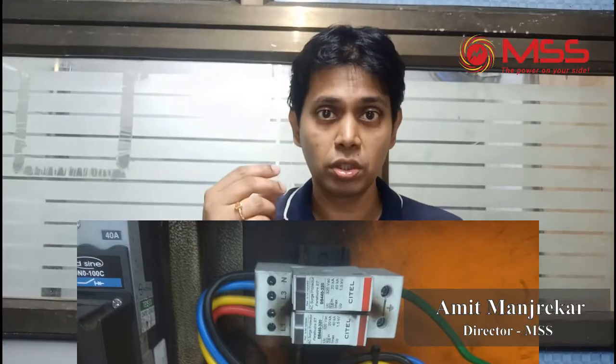Now, you may have noticed that the SPD might get damaged due to over voltage. There was one incident where an SPD was blown out and actually damaged — the neutral cartridge was damaged. Now this is where I want to educate you on certain things that can happen. When I was investigating what would have happened, I stumbled upon the datasheet of the SPD.